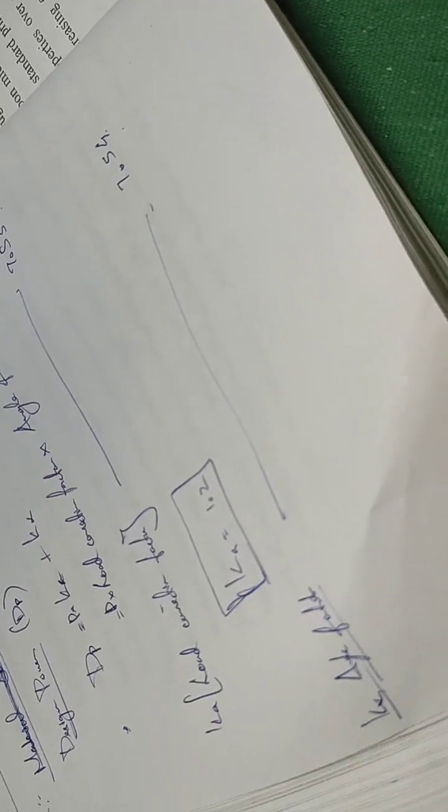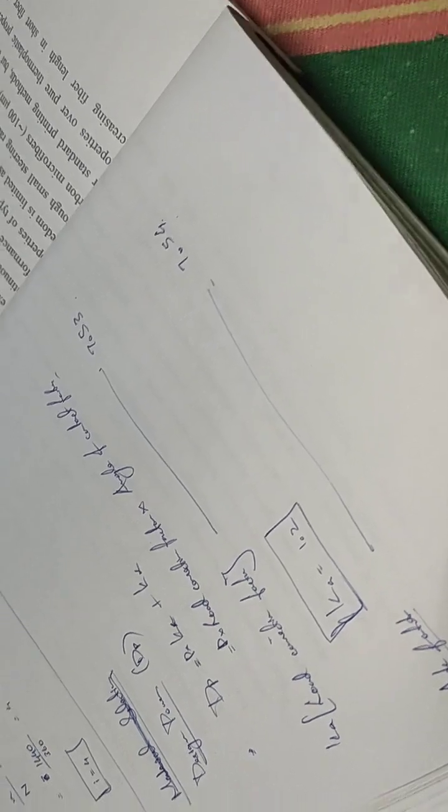From the question you should know what the load is. Here it is given as fan, so we took 1.2 as the load correction factor K value. The next is the angle correction factor, from 7.54. In the next page you will find the angle correction factor in the top.